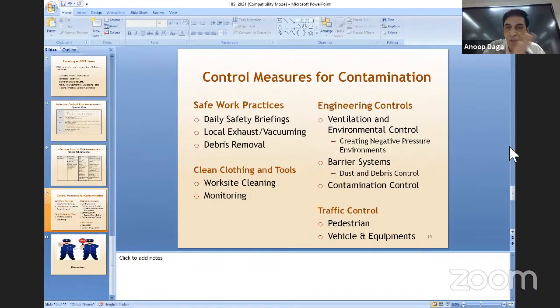Now for a cocooned facility like an operation theater, we will have a graded system so that the patient site for operation, that is the most sterile zone, gets the highest sterile air with the highest pressure from the air handling unit, so that area becomes the most sterile zone.